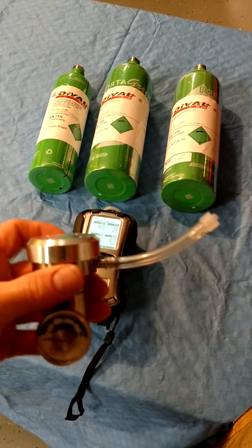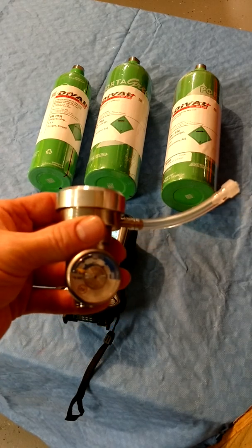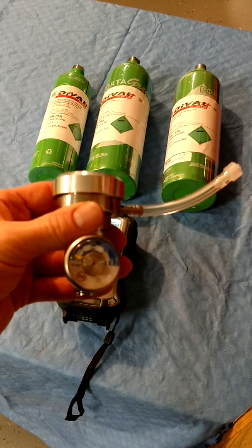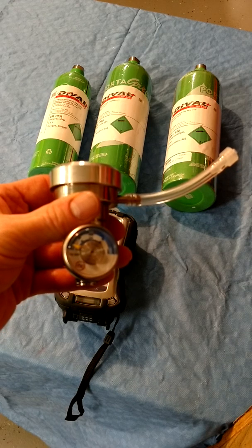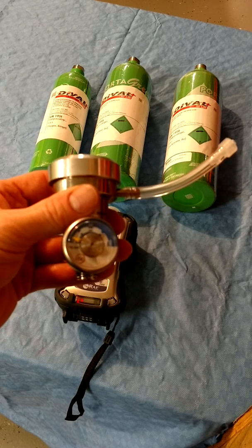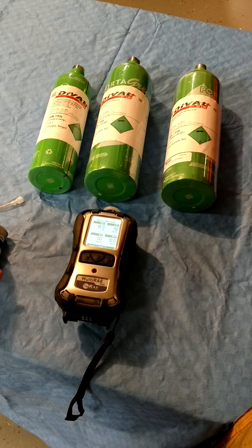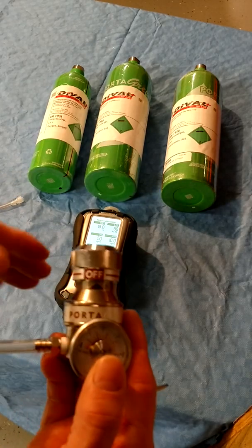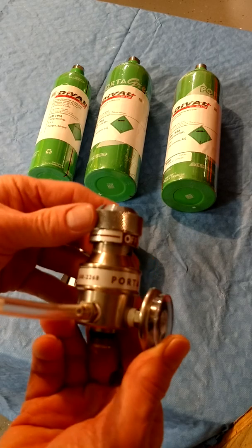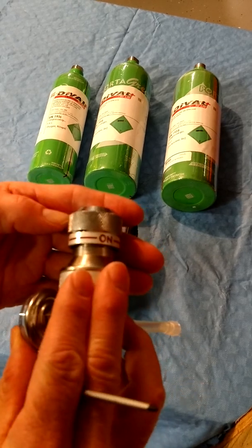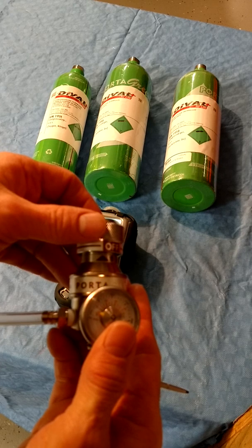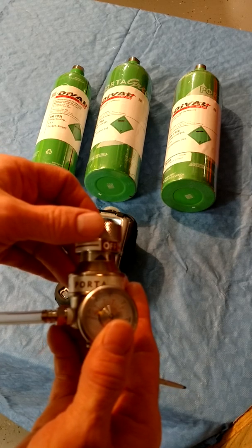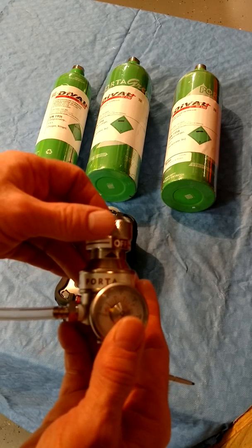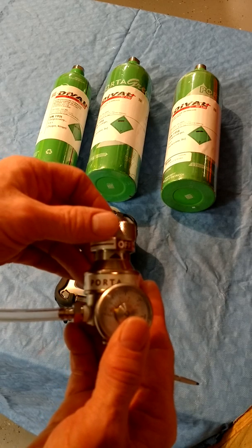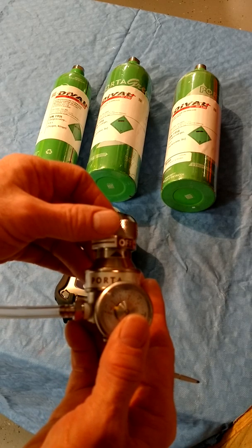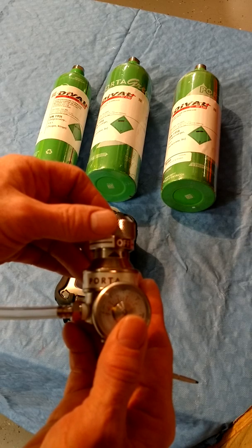Word about regulators. Some, like this one, are demand flow. Gas won't flow until demanded by the meter. Others, like this one, have a built-in valve with an on-off setting. Others may have a separate inline valve. If you use a valved regulator, ensure the gas is flowing prior to attaching the bottle to the meter to avoid stalling the pump.